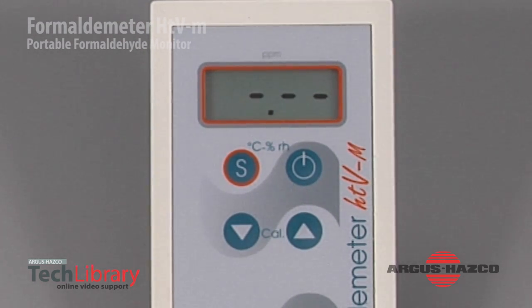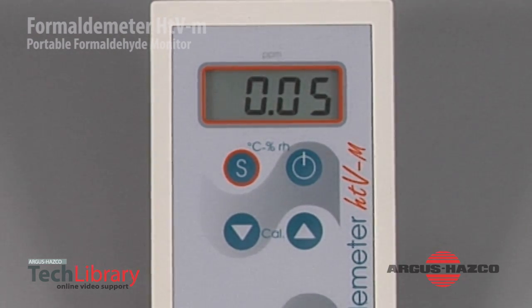As we're taking a sample, all the results are stored in its memory. The memory has a capacity of 1,000 samples, which can be downloaded using the software. You can also use this device as a continuous instrument plugged into AC/DC, and you can set your start and stop times through the software. The dashes will continue to flash until the sample is analyzed, and we have a concentration of 0.05. You can make a note of the concentration, and again, every sample is stored in its memory.